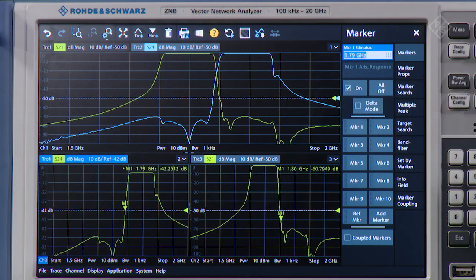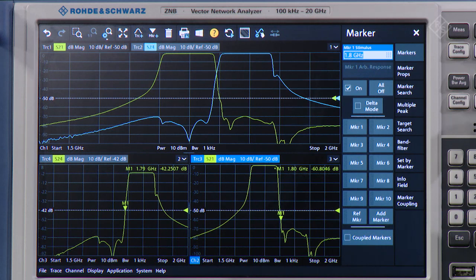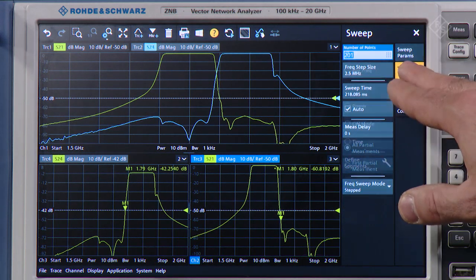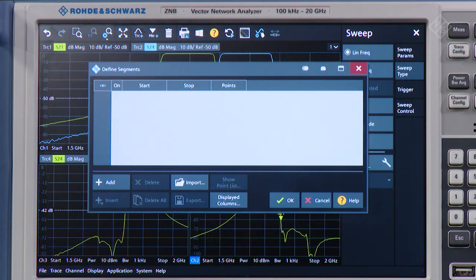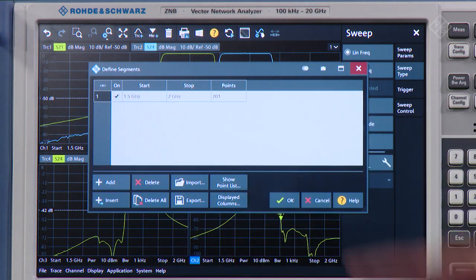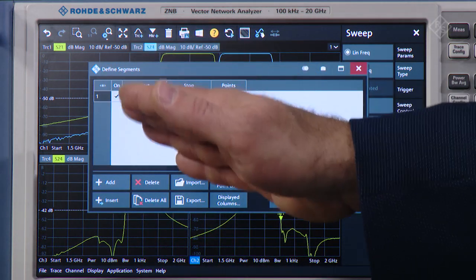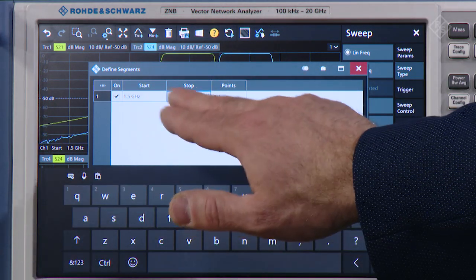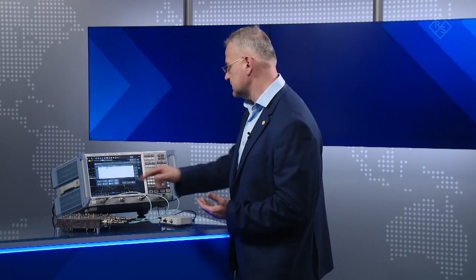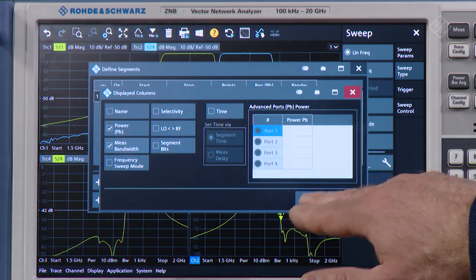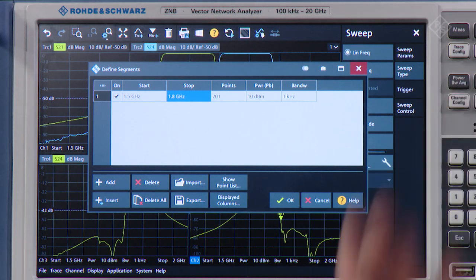We're ready to set up the segmented sweep. I will go back to the low band, go to sweep, sweep type, and select define segments. I will add a segment here and notice how the instrument automatically selects the desired frequency range. For the stop frequency, I will use my marker to set the frequency — that was one of the reasons why we added the markers. I will click on display columns and add two more columns: power and measurement bandwidth.